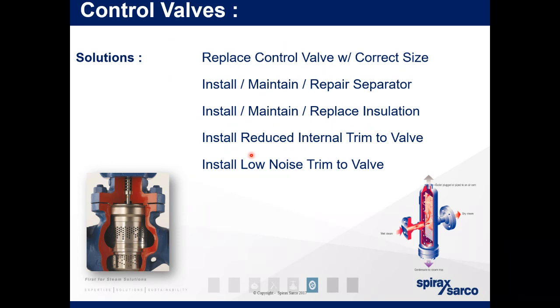Install, maintain and repair the separator. So a separator before the control valve will drop out any wet steam or any droplets from your wet steam, increase your dryness factor and protect the equipment which is downstream from it. So how the separator works, as you can see here, you have your steam coming in on your inlet. It hits a plate. The water that it's carrying, the droplets that are carried in that steam, will hit the plate and then work their way down through to a trap set. Steam goes over the plate, comes back through your outlet at a drier consistency.